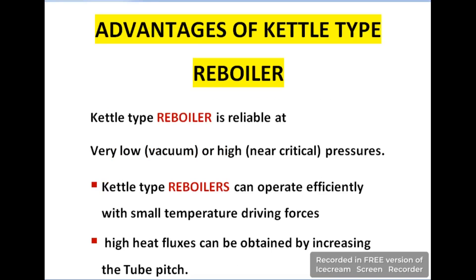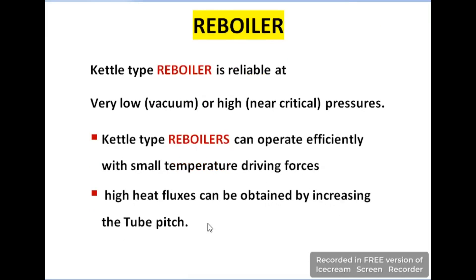Advantages of the kettle type re-boiler: First, kettle type re-boilers may operate at very low pressure as well as at high pressures. Second, kettle type re-boilers can operate efficiently with a small temperature difference. Third, high heat fluxes may be obtained by increasing the tube pitch of the tube bundle.